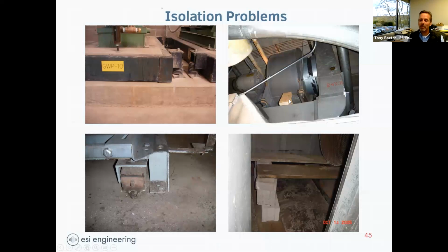Not the best maintenance, but the one that has always been the worst example ever - this is inside an air handling unit in a hospital. I was tracking down this vibration source, opened up the door, and here, this was a return fan in an air handling unit. I could not believe it was propped up on CMU blocks and 2x12s. It just blows my mind that they had been operating like that.